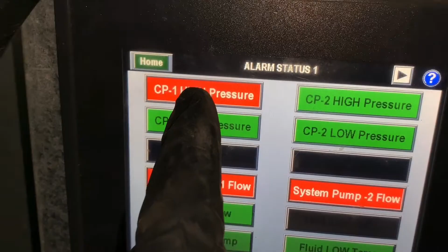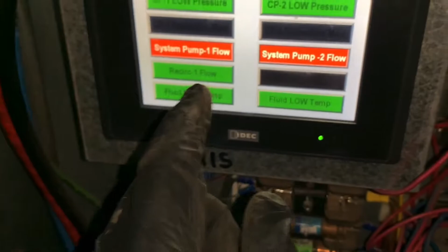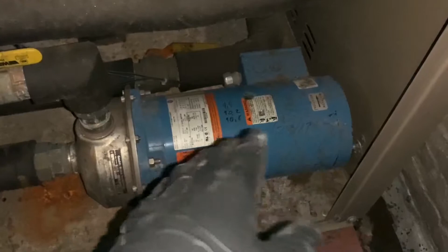We got some alarms here. We got high pressure on compressor 1, which is the one over there, the one that I was looking at with the headmaster. And we got some pump flow issues. I don't know what's going on with the pumps. I mean, the pump is running, that's running. That's a primary and backup, they both pipe together into that loop.